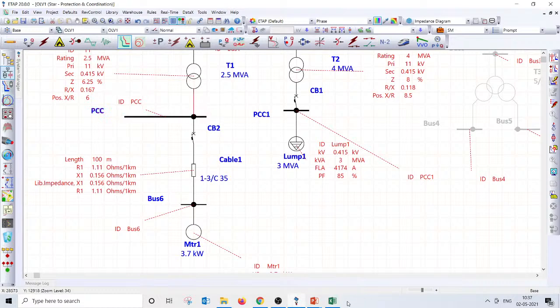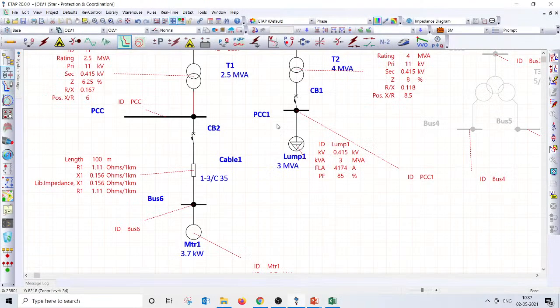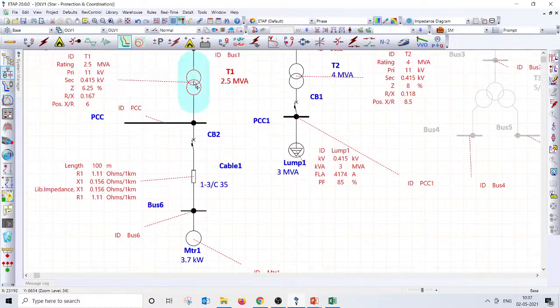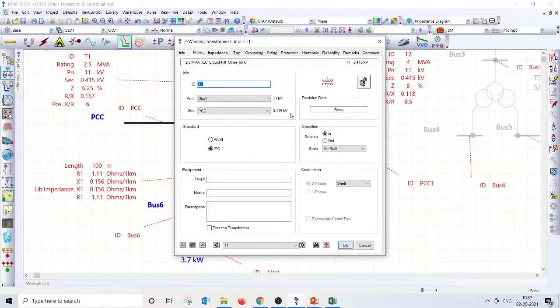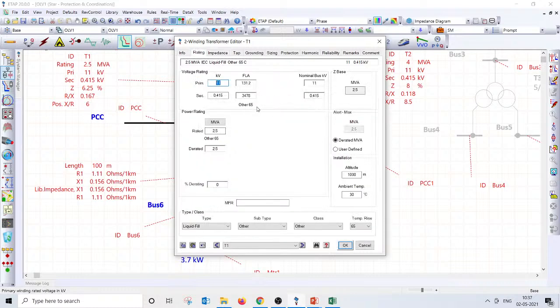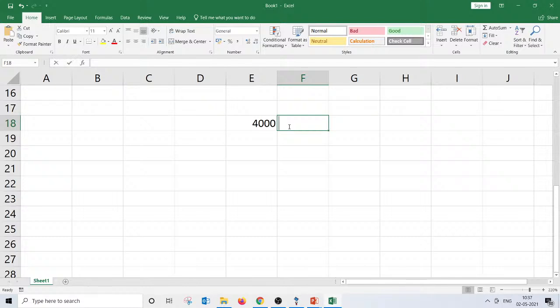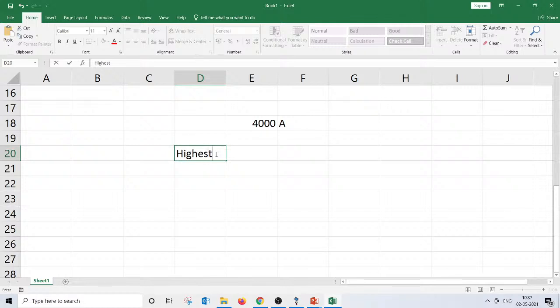like the incoming current rating versus the outgoing current rating. So the incoming breaker we have selected is 4000 amps, right? For the incomer selection, the full load current is 3400 and something, 3478. So you have an incomer breaker rating of 4000 amps. And what could be the highest outgoing from this PCC, and what would be the lowest outgoing from the PCC, which we can put?